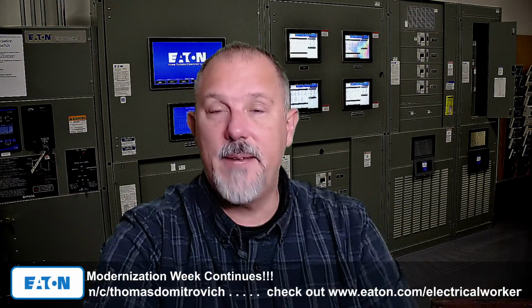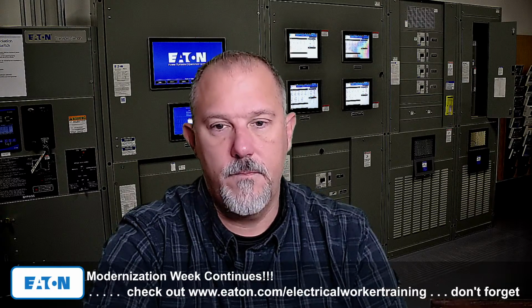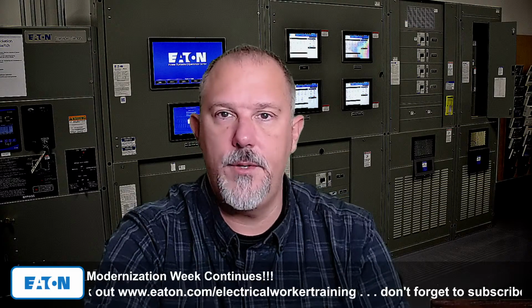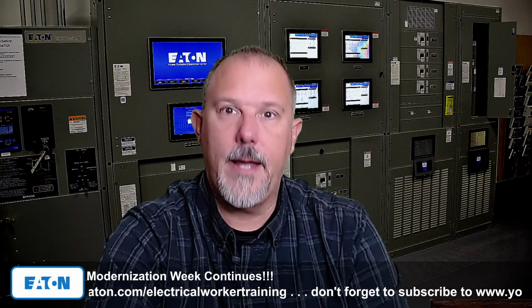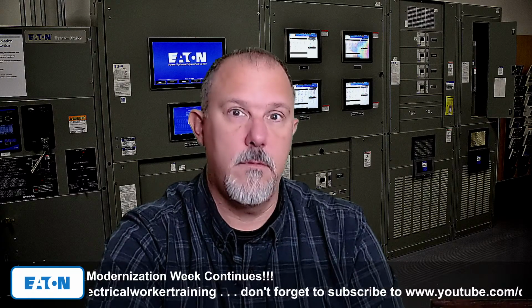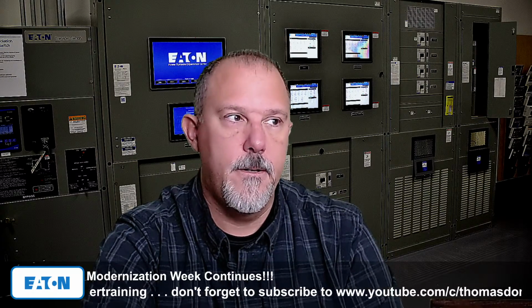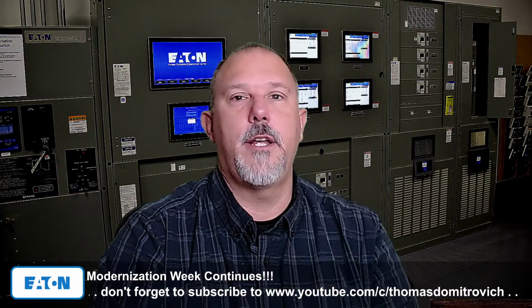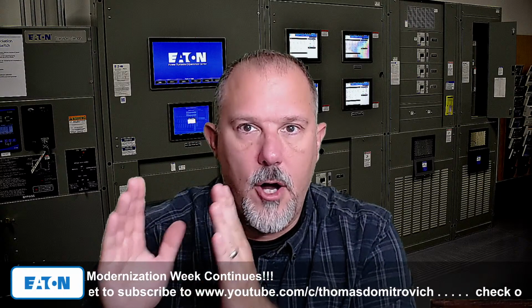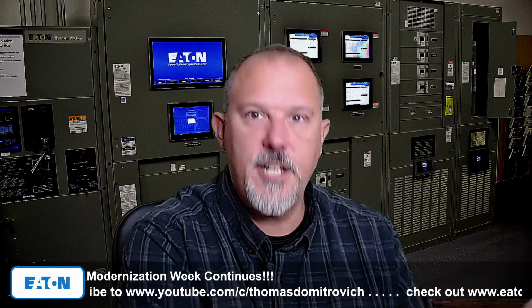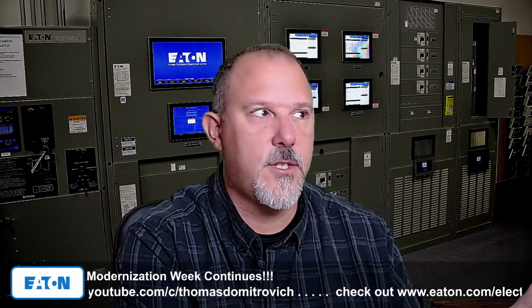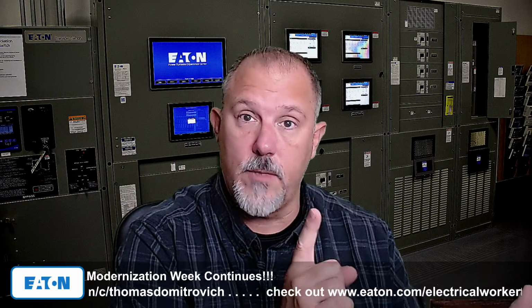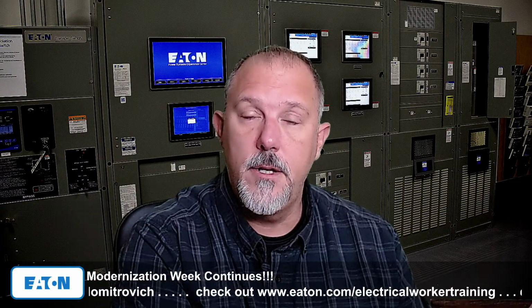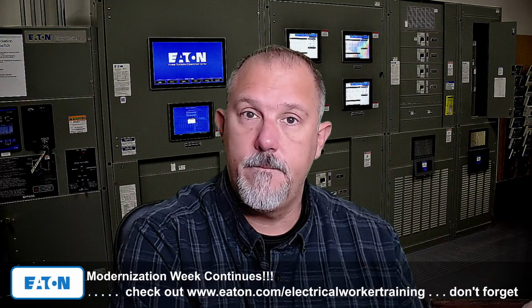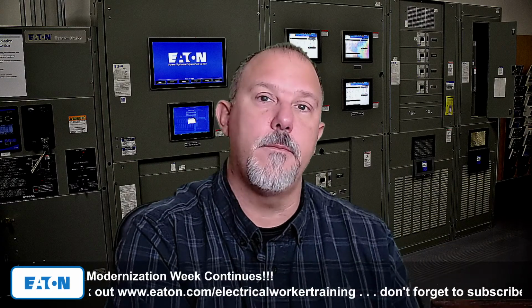Yet HVAC, 60 amp circuit, we want to give forgiveness. We just say that's the way it is. Why? Because it's tripping a GFCI. And rightfully so. Why is it that we hold a double standard between the occupancy sensor and an HVAC condensing unit that's installed outside that has already killed at least one child and others based upon CPSC data? Why the double standard? I don't think it should be there.